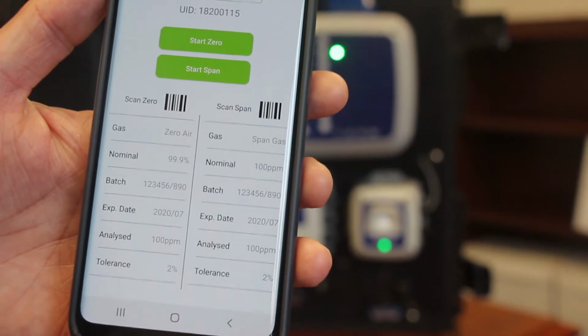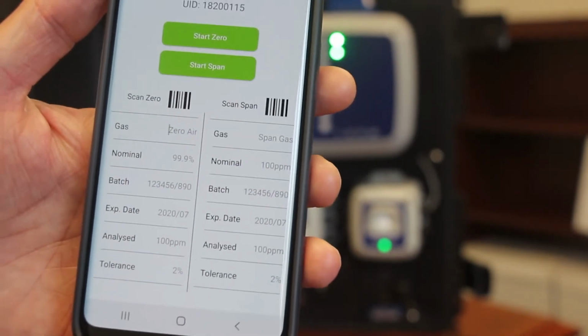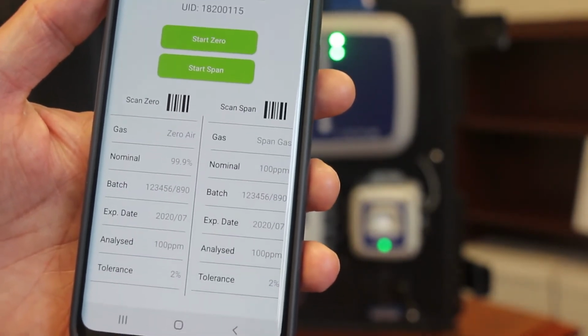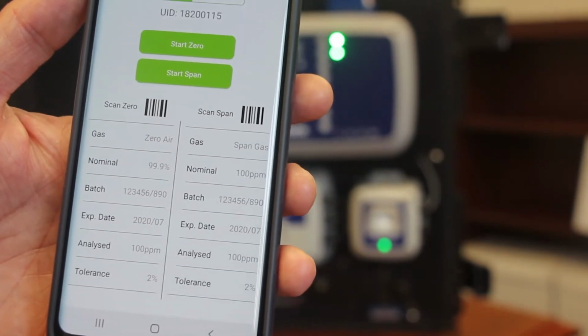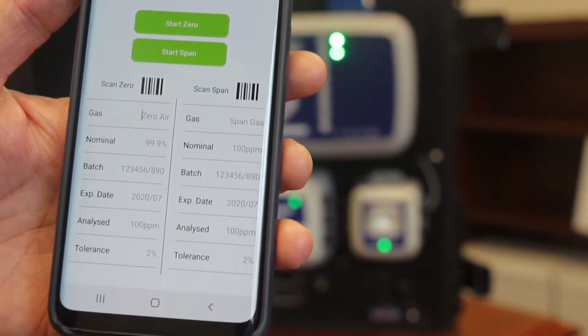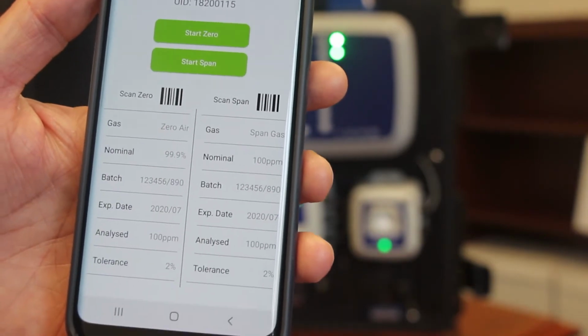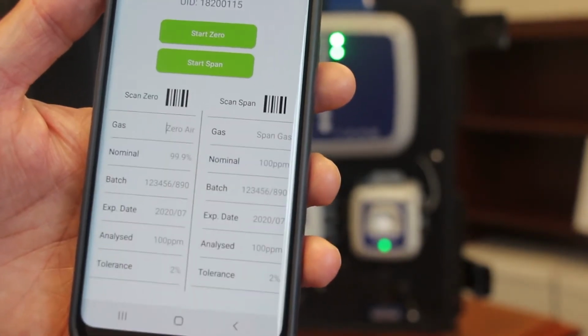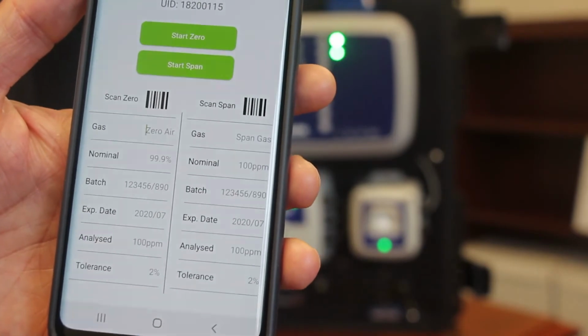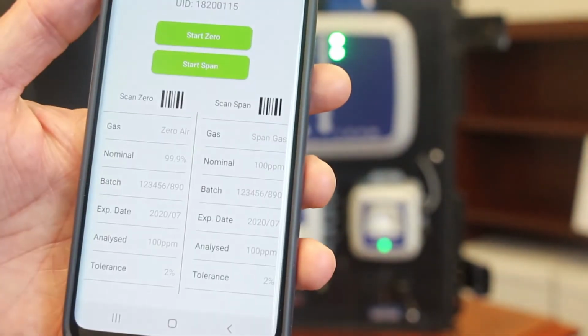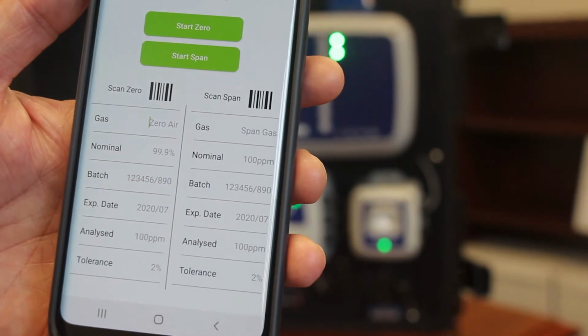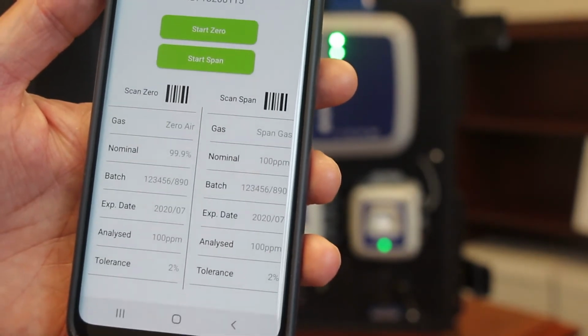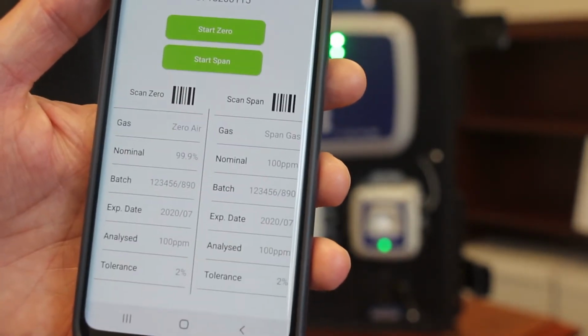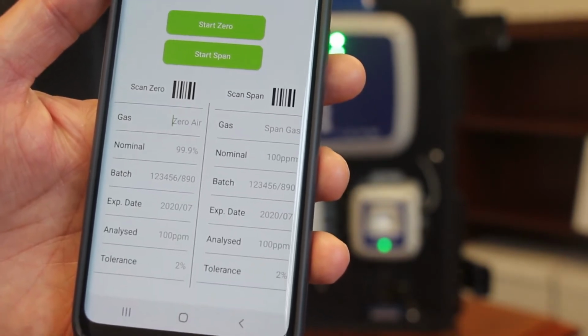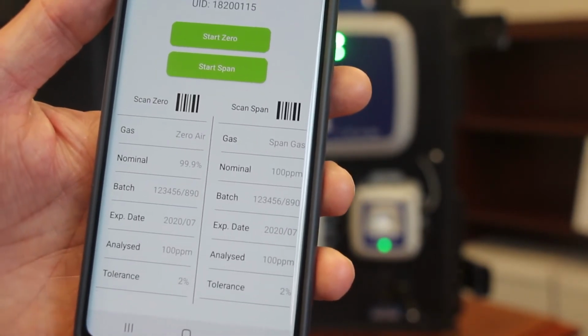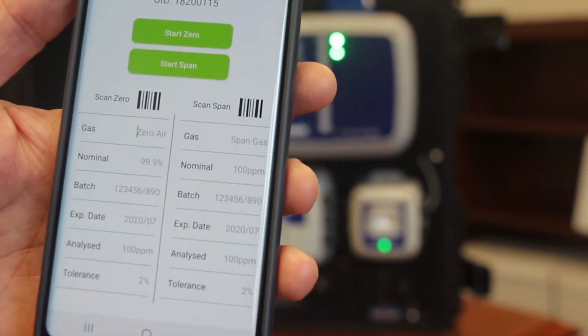When you start the span calibration, you simply have the calibration adapter attached to the front of the detector with your calibration cylinder and tubing, and you simply switch the calibration gas regulator to on. It will flow the gas across the detector, and it will automatically go through that calibration process. Once the calibration is complete, you'll get a notification to say that the calibration has been successful. And at that stage, the app will automatically generate a calibration certificate for that detector.